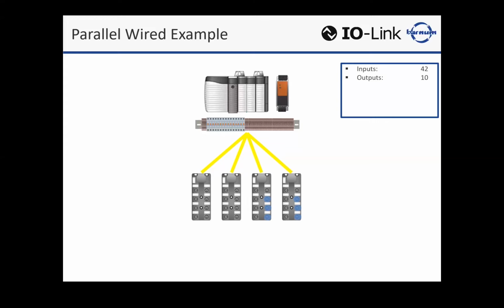Maybe add a couple remote boxes? Yeah, on any piece of equipment, even if you have a main PLC, you're going to have some remote HMI boxes, or human machine interface boxes, where you're going to have maybe a stack light, a couple selector switches, push buttons along with your HMI, just because there's some functionality that needs to occur at that station. All right, let's add 2 of those. And again, those are hardwired directly back to the PLC.